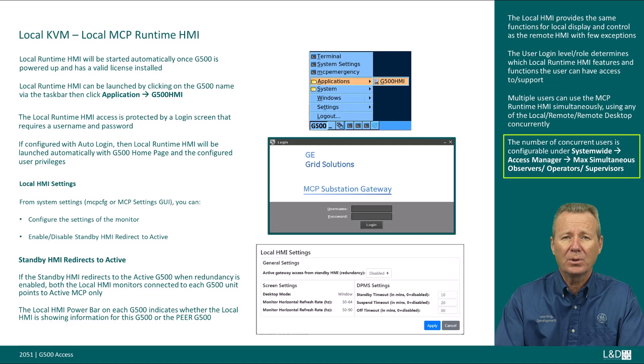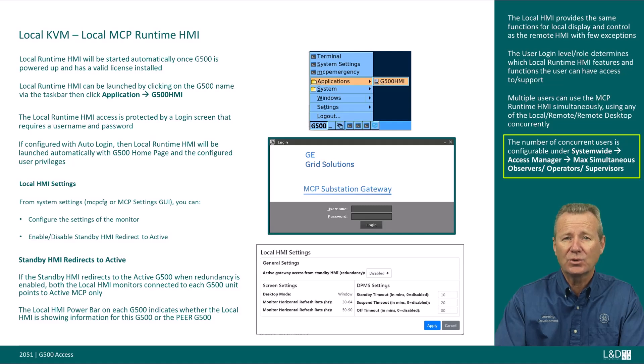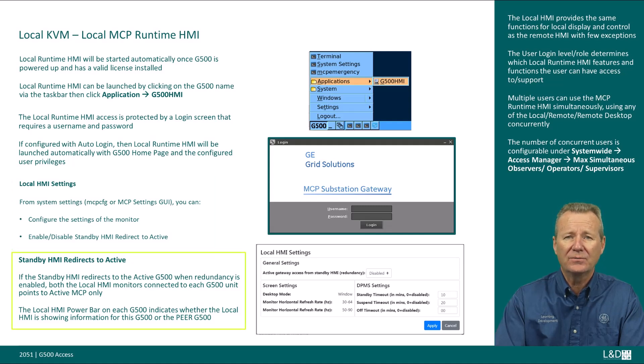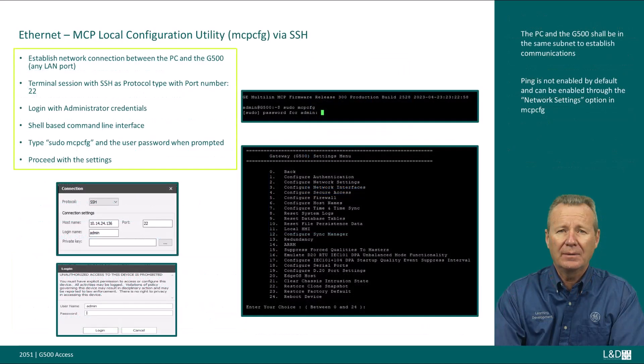Multiple users can use the MCP runtime HMI simultaneously using any of the local, remote, or remote desktop sessions concurrently. The number of concurrent users is configurable under system-wide access manager max simultaneous observer, operators, and supervisors in the DSAS MCP Studio configuration tool. You can configure the settings of the monitor connected to the display port and enable or disable the standby HMI redirect to active through the local HMI menu of the MCP utility or the MCP settings GUI. If the standby HMI redirects to the active G500 when redundancy is enabled, both local HMI monitors on each G500 unit point to the active MCP only.